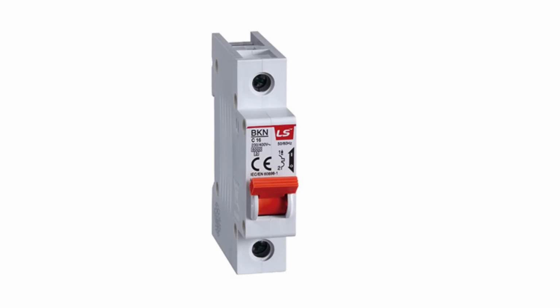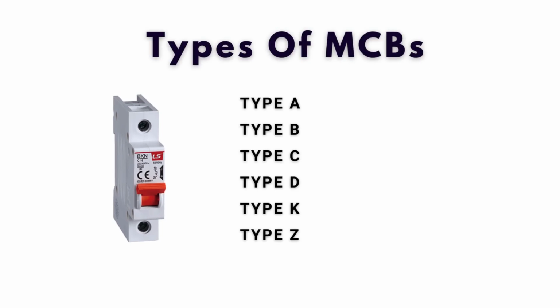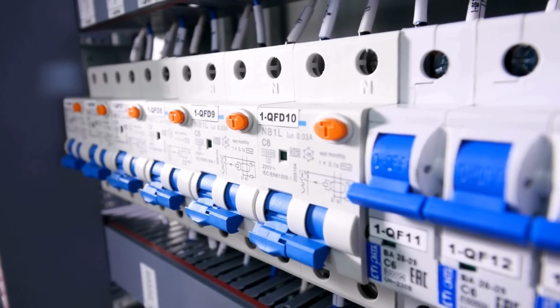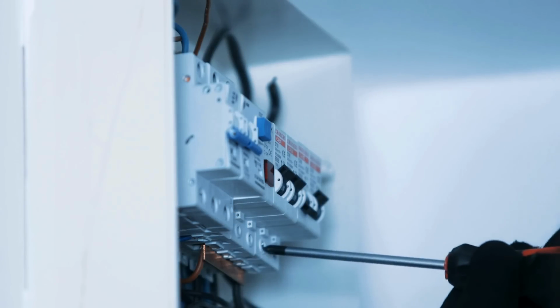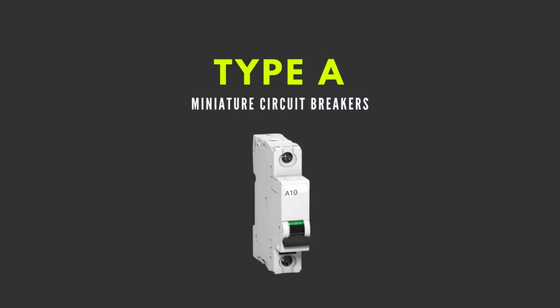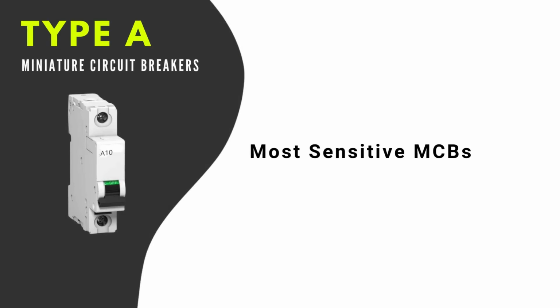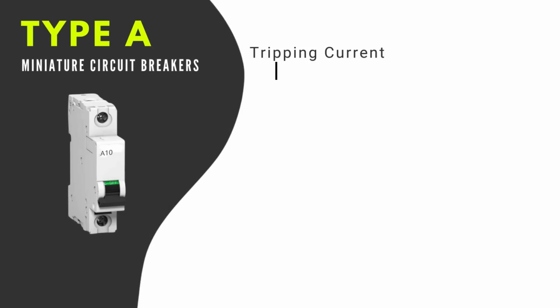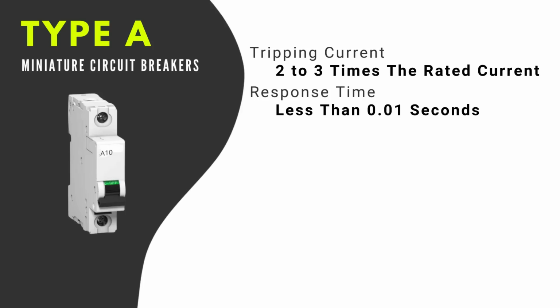In this video, we'll explore the different types of miniature circuit breakers, or MCBs, their characteristics, and where they're used. First up, we have Type A MCBs. These are the most sensitive, tripping at just 2 to 3 times the rated current. They react instantly, with a trip time of less than 0.01 seconds.